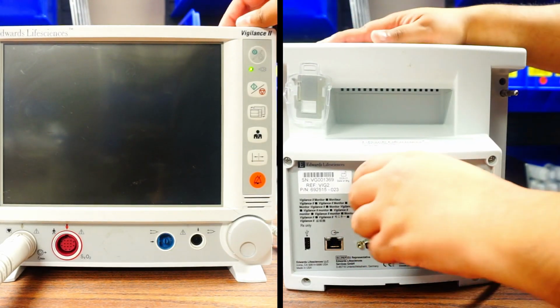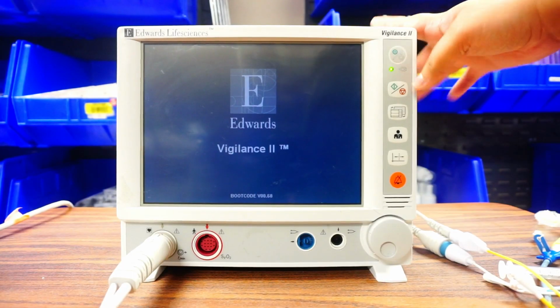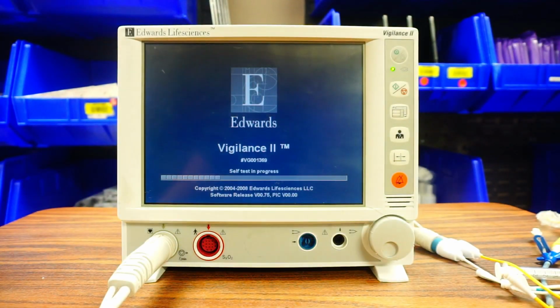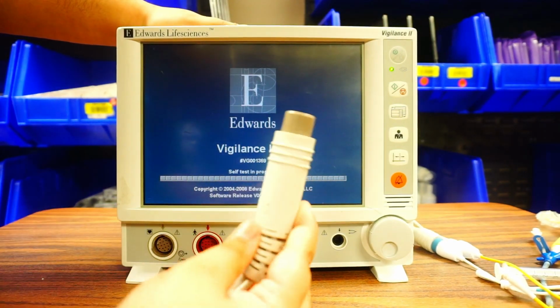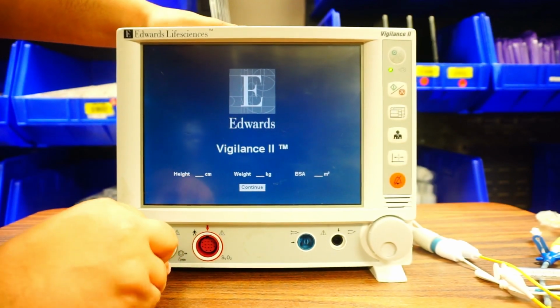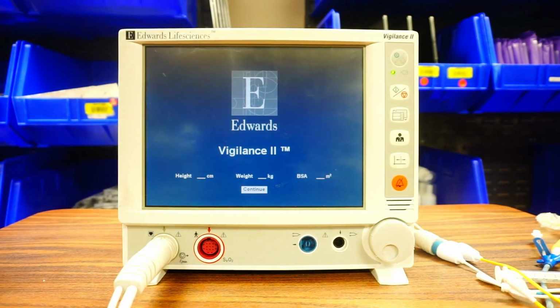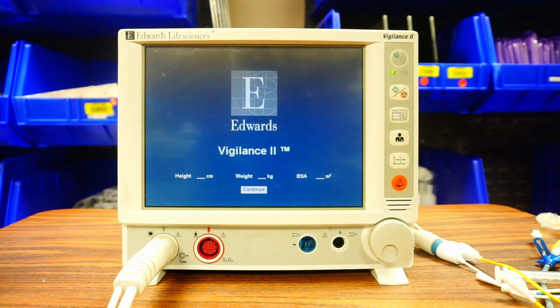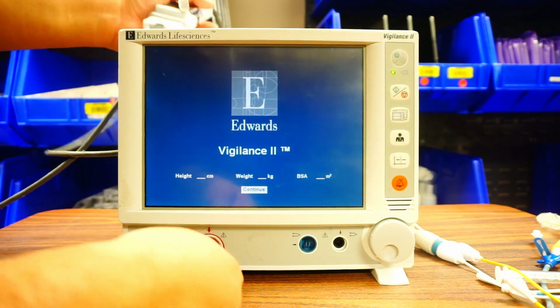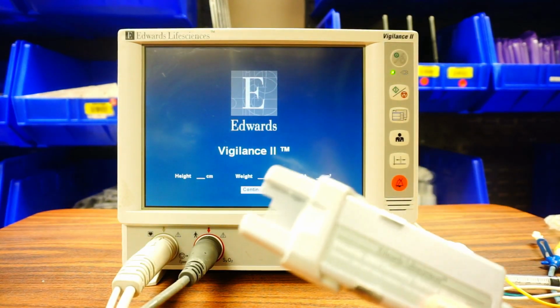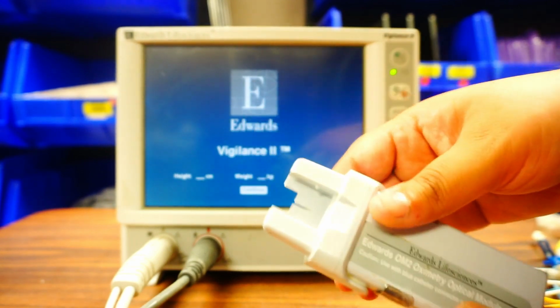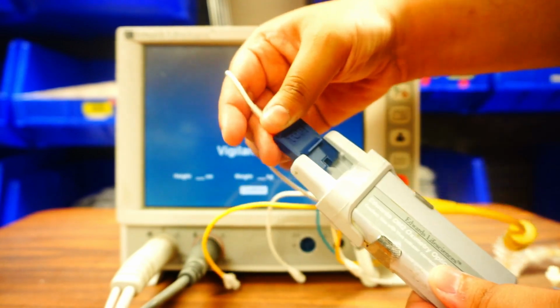The plug-in cord for your Vig 2 is going to be in the back. The button's going to be here, so you're going to go ahead and press that on. As far as your cord connections, the same gray cord that we used for the Hemisphere is still here. Going to plug into our gray here, and then we have a red cord similar to your Hemisphere, but the end of this cord will look different. This is one of the changes that Edwards made whenever they were updating the machine. You still have your red end of the cord, which is going to plug in here. The end of the red cord is going to look different. Instead of the clip, you're just going to slide in the blue clip here and press it in. You'll hear a click and those securements are made.